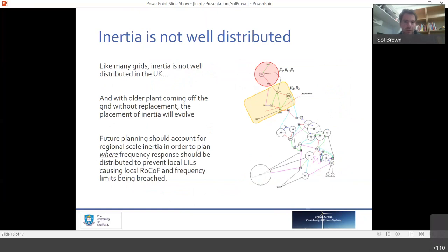And just before I finish off, I wanted to mention in passing the importance of inertia as a local thing. Particularly in the case of the UK, we're having large synchronous generators shut down across the country. Whereas there was an amount of planning in place so that they would provide inertia where required, they're now coming off, and we're not able to control that in the same way. So inertia is going to become an increasingly important thing, whether that's real inertia or synthetic inertia, and I think that is a very key point going forward in system planning.